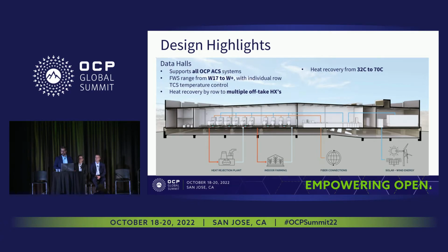Along those lines, we can design and accept any type of facility water ranges. We can control each of the rows, the pod rows, from a thermal and temperature perspective such that we can export heat in a very specific manner and at strategic exits to our heat recovery highway. As we evaluate the grade of heat we're getting back from a rejection perspective, we can take it off at strategic points, allowing us to have a recovery system capable of recovering anywhere from 32 to 70 degrees C—a very wide, very agnostic system design.